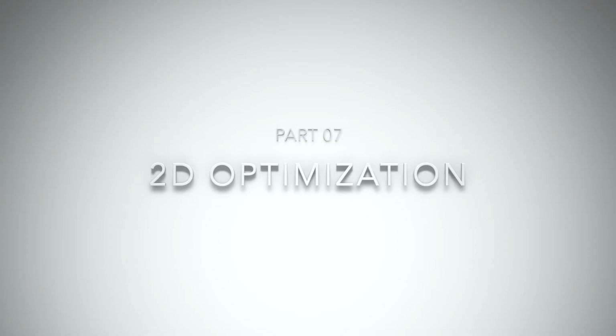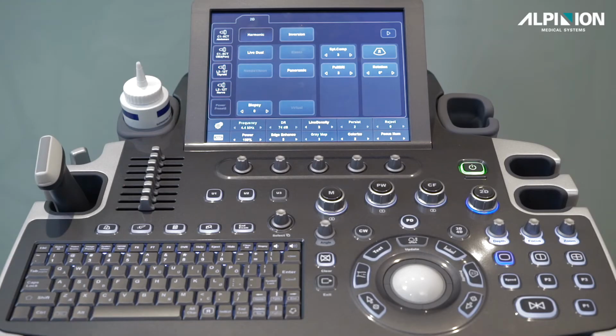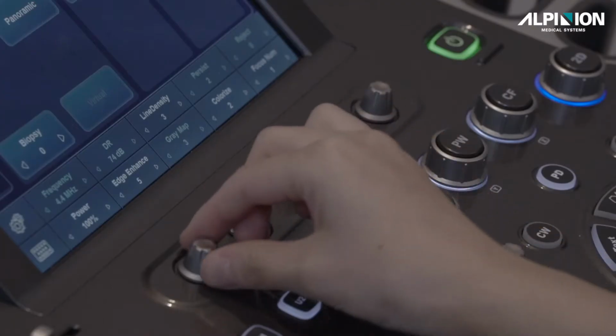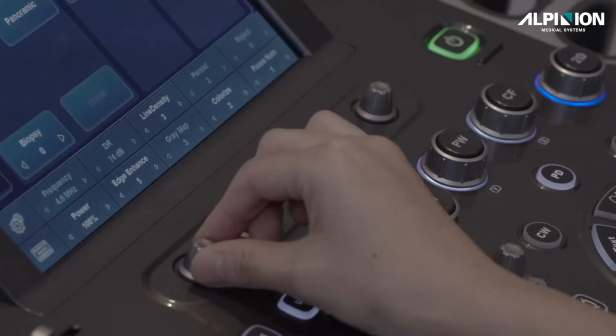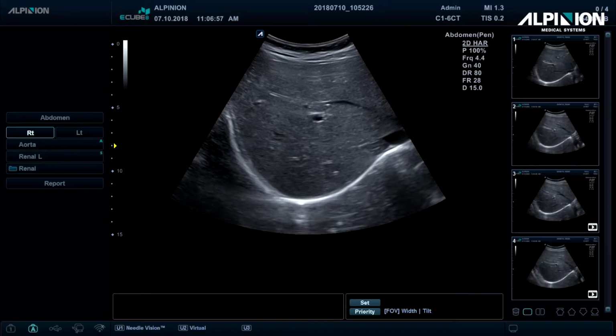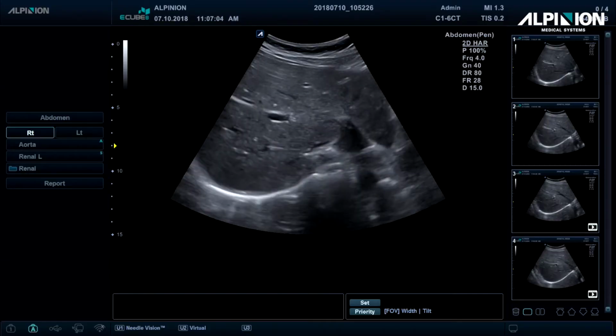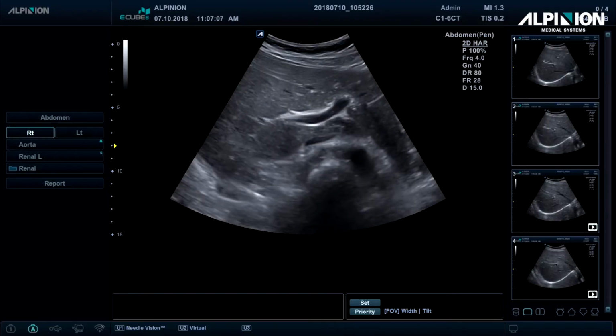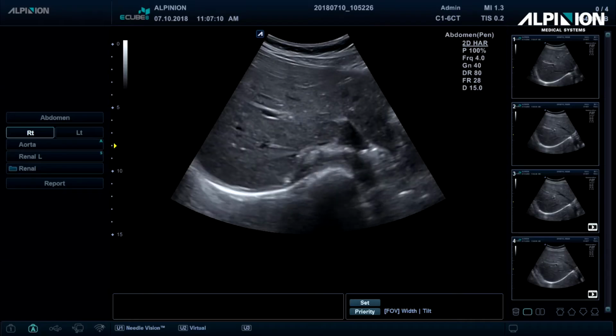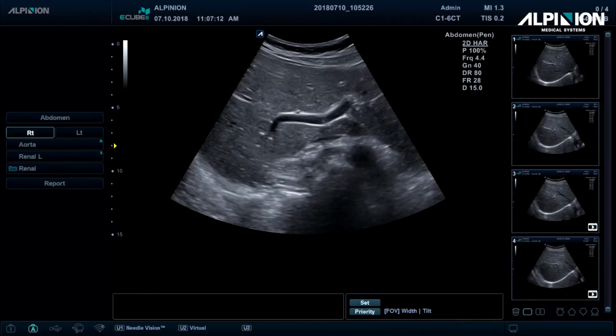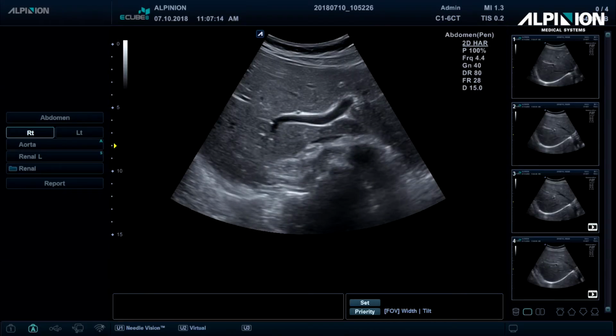Part 7. 2D optimization. Now I will look over the basic imaging parameters that are commonly adjustable while you are imaging. Frequency. The first thing you can adjust is frequency. Adjusting the frequency allows you to increase penetration at the expense of resolution, or increase resolution at the expense of penetration. Our system offers around 5 center frequencies in fundamental and harmonic modes. So depending on your exam type and patient case, you can adjust your frequency as you want.